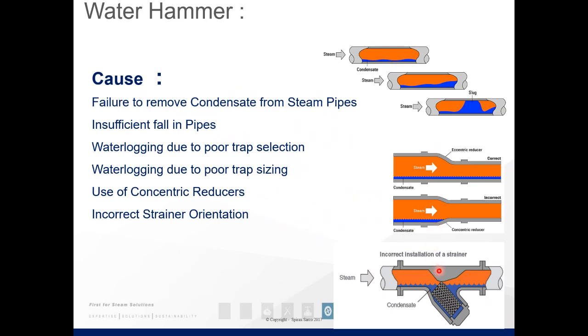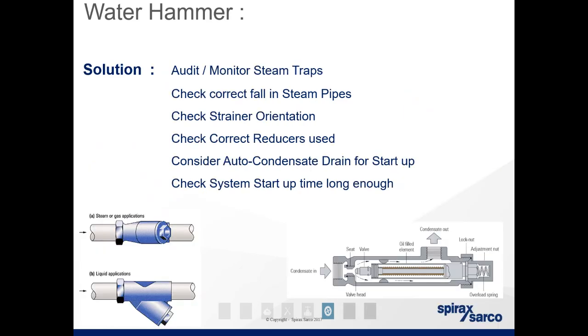As alluded to earlier in the training, also the direction of your steam strainer. This is the perfect position for a condensate line. Imagine this pipe is full of condensate. Particulates come into the strainer and drop into it, and the condensate moves out. If this is on a steam line, however, you have an area where you can build up condensate, and therefore build up the potential for a slug down your steam system. So on all steam systems, the strainer basket should be facing towards us, on a horizontal plane, which I will cover in the next slide. As you can see here, a steam line, horizontal plane, trap, liquid condensate. So we drop it to the bottom.